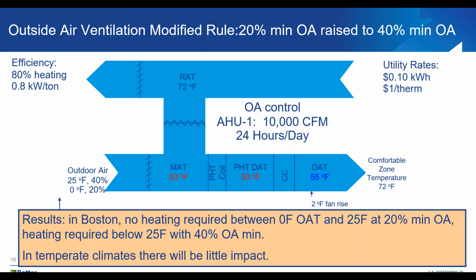If we're talking about an environment like Boston, under the old conditions, if the economizer was working properly, you could get down to 0 degrees without even needing any heat to provide the amount of heating in this specific example of an air handling unit. However, if you have to bump it up to 40% outside air minimum, then you can only use the economizer down to 25 degrees before you require additional heating. So there's going to be additional heating as a result of it, and you need to make sure that your system size is large enough to provide the heating.